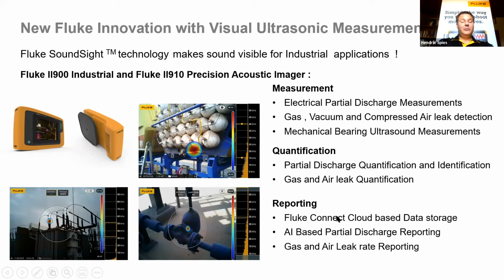It connects to our Fluke Connect cloud-based system, where we've got a database where we can store all your images, and we've got AI-based partial discharge and leak quantification algorithms running in our equipment. So gas and air leak reporting, partial discharge reporting, and mechanical bearing and ultrasound reporting. So it's a very nice new technology that actually makes sound visible to you as the customer.